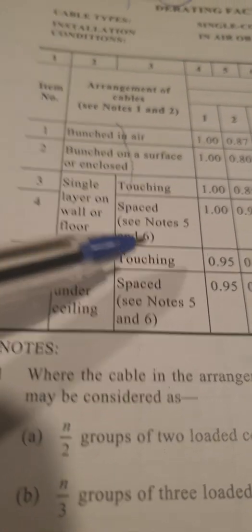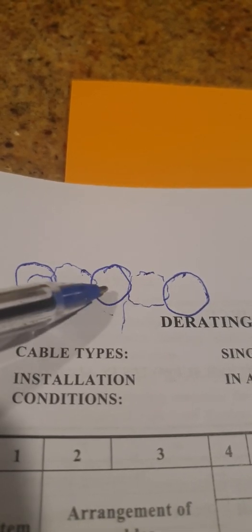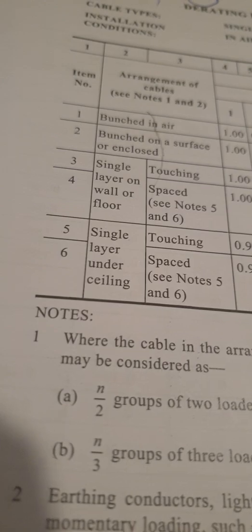Spaced means that we have to have one distance, and it is to allow for heat to get away. If we have them touching, then there's no space distance at all. What they're giving as a minimum requirement is the cable has to be one minimum diameter of the cable. So if I'm going to do that, I would lay another cable in between - that would be my spacer, and then we would lay that apart.